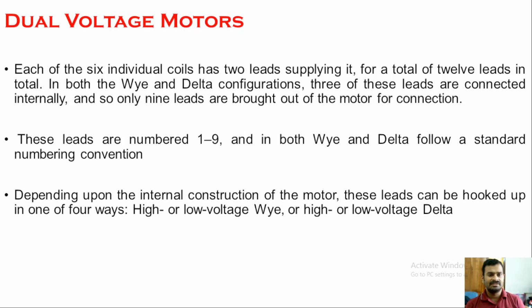If it is a 9 wire motor, the wires or the leads will be numbered from 1 to 9 in both star connection and delta connection. So based on these voltage wiring connections, you can have either high voltage or low voltage star, or high voltage or low voltage delta connection.